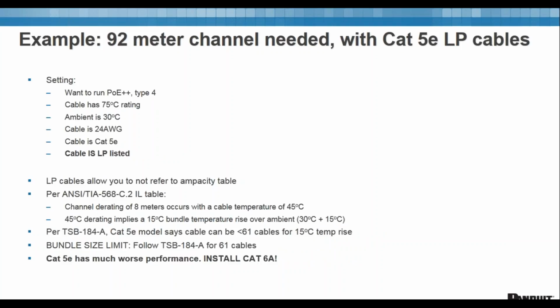Now, if you've got a 92 meter channel with Cat 5e LP cables, again, because it's an LP rated cable, you don't have to be as concerned about the bundle size limits related to the NEC. But now, per ANSI TIA, you have to worry about this 8-meter derating at 45 degrees Celsius. Per TSB 184A, you have to have 61 cables or less for a 15-degree temperature rise, right? Because this 8 meters occurs at a cable temperature of 45 degrees C, and we're saying the ambient is 30, so 30 plus your 15-degree temperature rise is 45. And 61 cables gets you to that 15-degree temperature rise. So if you're using a 5e cable to run that, you're going to be limited to about 61 cables. 5e does have worse performance. Our recommendation is to install Category 6A.